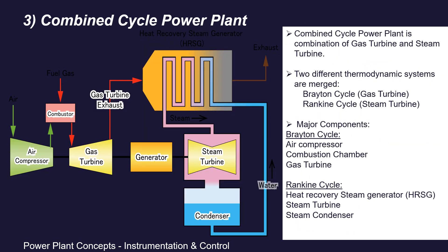Next is the combined cycle power plant (CCPP). We have already discussed the simple open cycle gas power plant based on the Brayton cycle, where exhaust gas carries a lot of unused energy into the atmosphere. In a combined cycle power plant, this unused heat energy is used to produce steam and rotate steam turbine blades, thus producing additional electricity. A combined cycle power plant consists of two thermodynamic systems: one for the gas turbine operation (Brayton cycle) and one for the steam turbine operation (Rankine cycle). On the gas turbine side: air compressor, fuel gas combustion chamber, and gas turbine. On the steam turbine side: heat recovery steam generator (HRSG), steam turbine, and condenser.